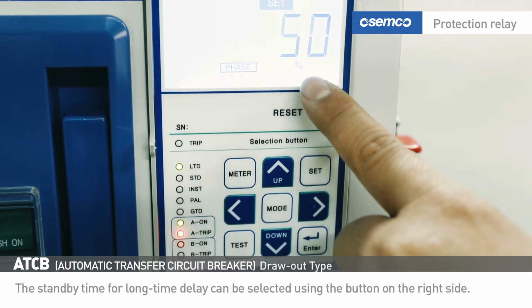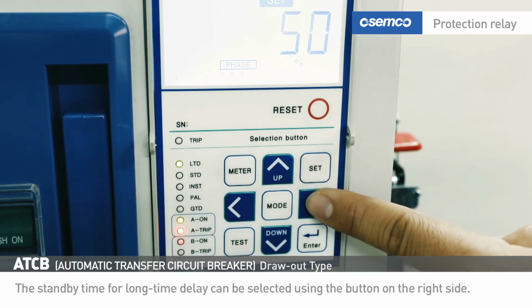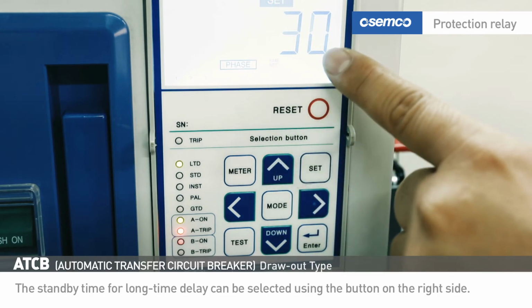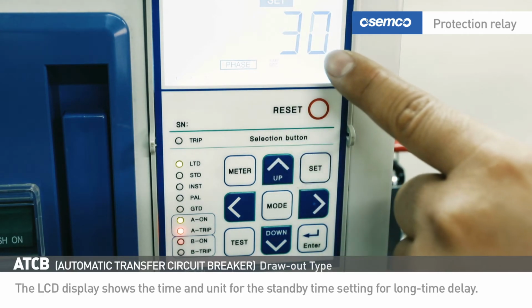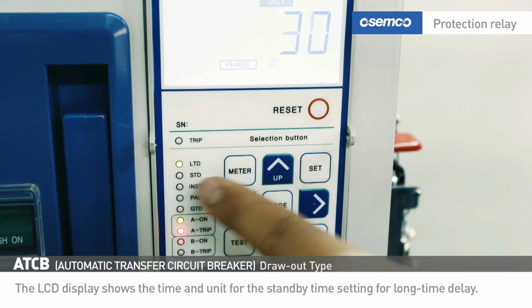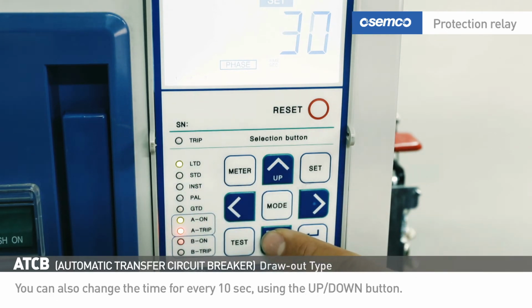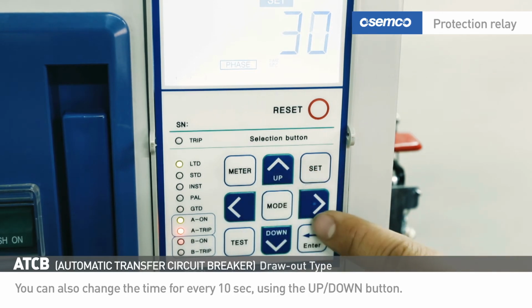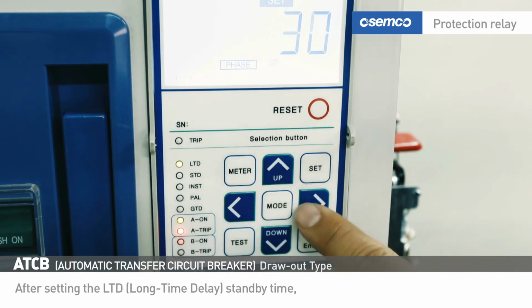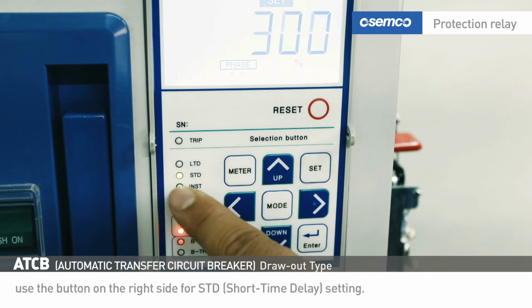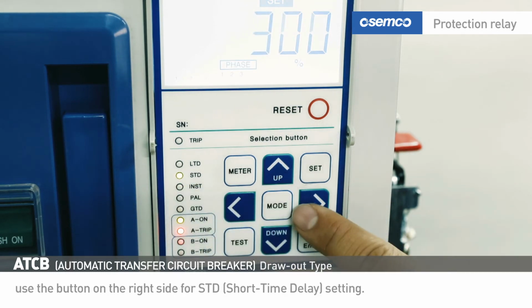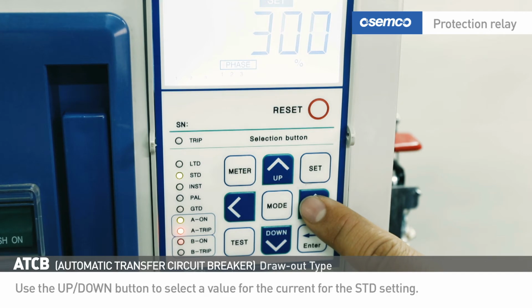The standby time for long time delay can be selected using the button on the right side. The LCD display shows the time and unit for the standby time setting for long time delay. You can also change the time for every 10 seconds using the up-down button. After setting the LTD, long time delay, standby time, use the button on the right side for STD, short time delay setting. Use the up-down button to select a value for the current for the STD setting.